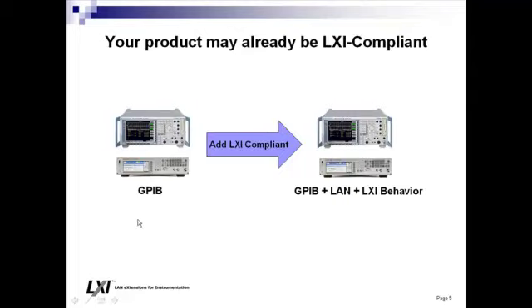You may be thinking of your instrument in a test system with a GPIB connector, but maybe it already has a LAN port. And if that instrument has LXI compliance, that LAN port provides the LXI behavior you can rely upon — giving you ease of integration, access to the built-in web server, and the ability to build test systems more quickly.